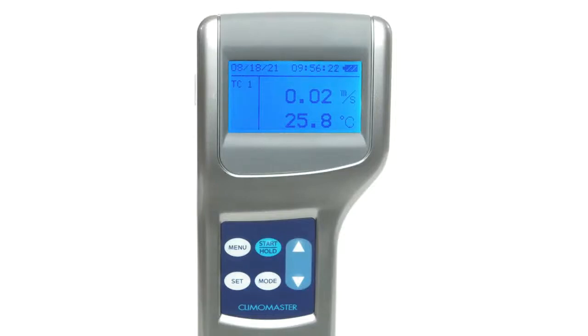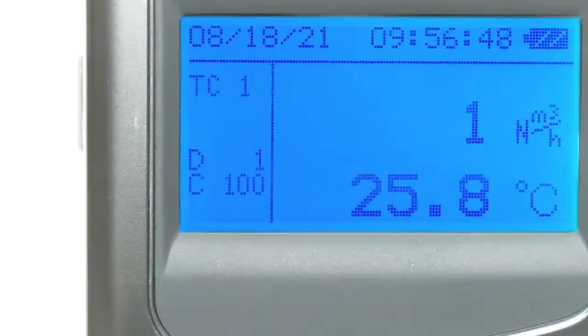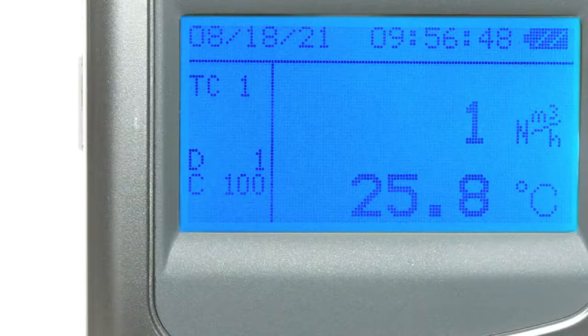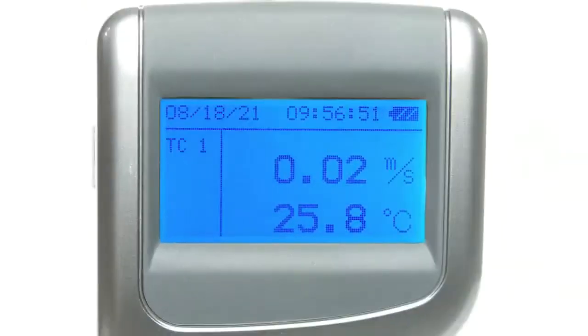The item changes with each press in the following sequence: pressure, flow rate, air velocity. When measuring flow rate, you can find the selected duct type in the lower left corner of the screen. If you need to change it, you can scroll to it using the navigation buttons and select it with Set. As mentioned before, while measuring in normal mode, pressing the Start or Hold button will hold the current reading. This is applicable in both the flow rate and pressure measurement screens as well. The hold indicator appears on the display to indicate that the reading shown is being held. To release the reading, you just press the button again.